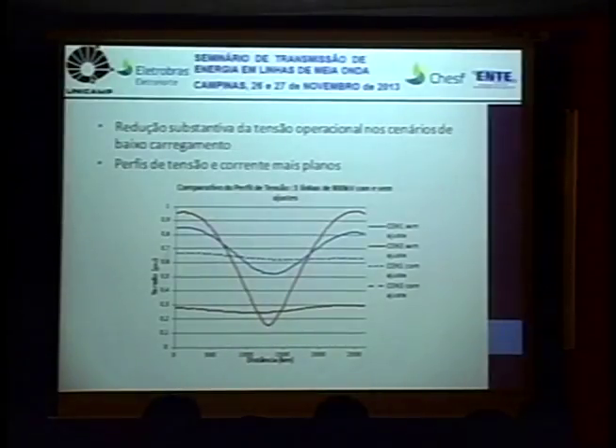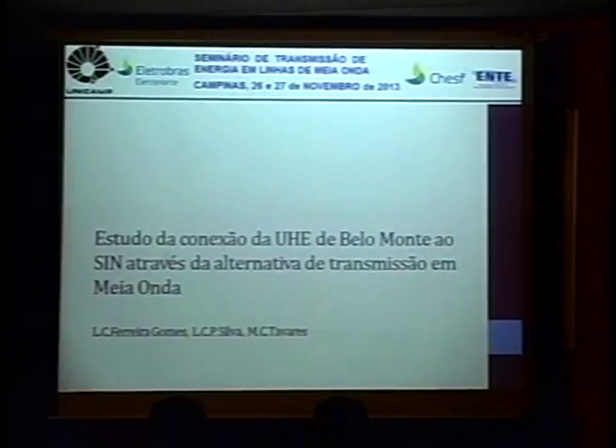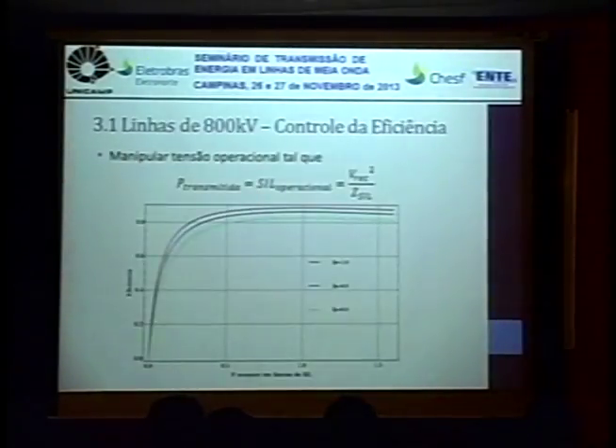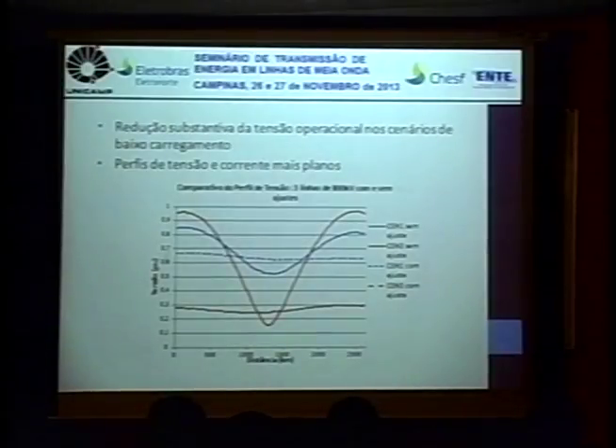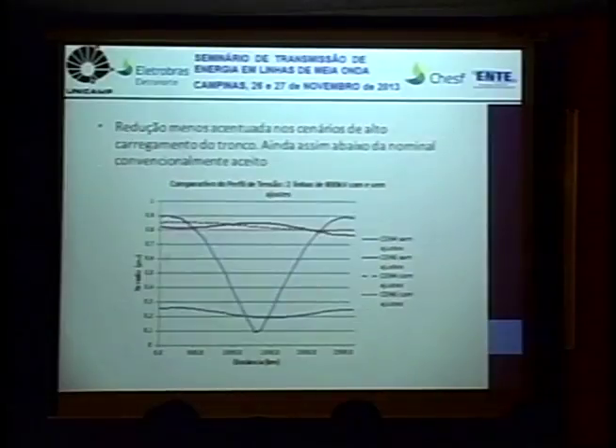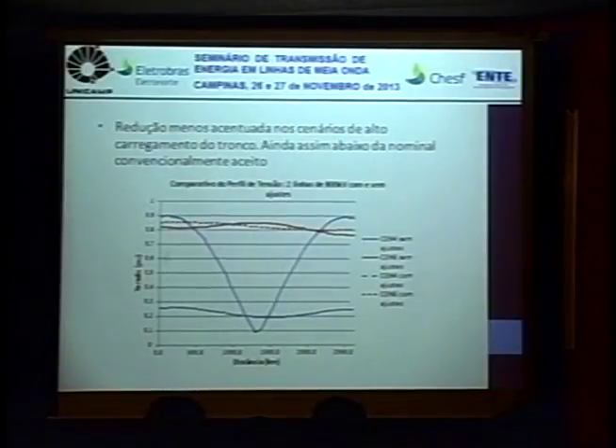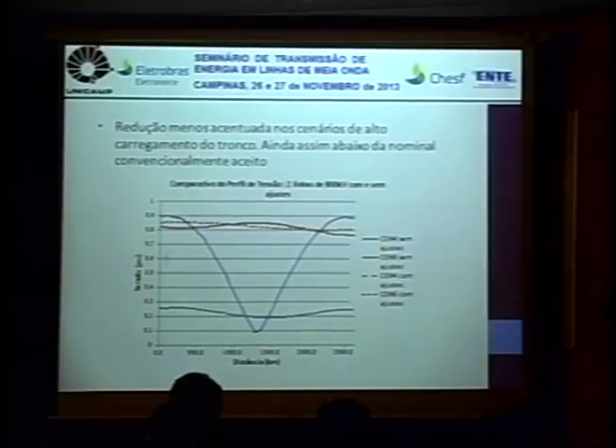Here we saw the voltage profile for some scenarios, before the adjustment and after the adjustments. Since the line is close to the characteristic power, it gains that voltage profile we are used to, which is flat. This flat profile, because the line is operating near to the characteristic power. But look at this. In this scenario, it's an 800 kV, but it's operating near to 0.3 pu, 240 kV. Here, it needs to operate close to 0.7 pu, so a load which is a little larger. Here, the load is a little bit closer to the original characteristic power value, so we can make it become closer to 800 kV. It's only going to operate with 800 kV if the transmitted power is higher.